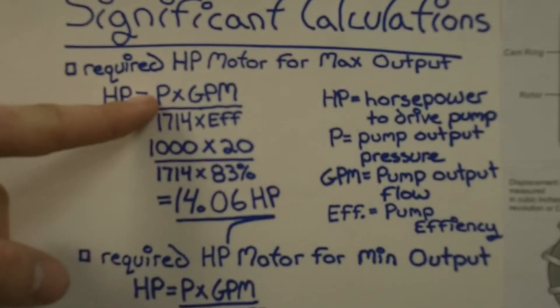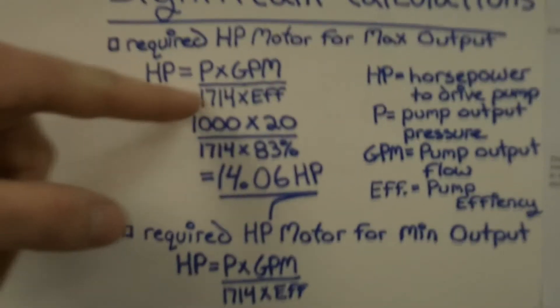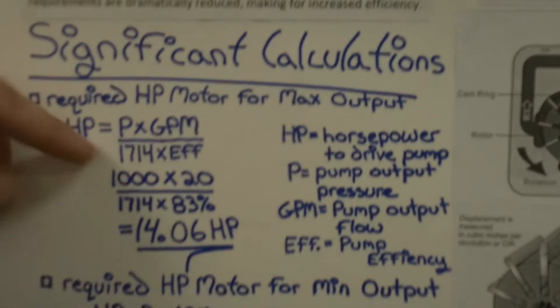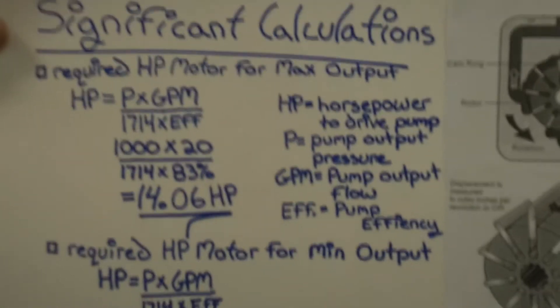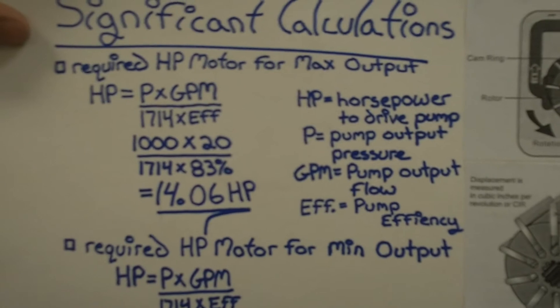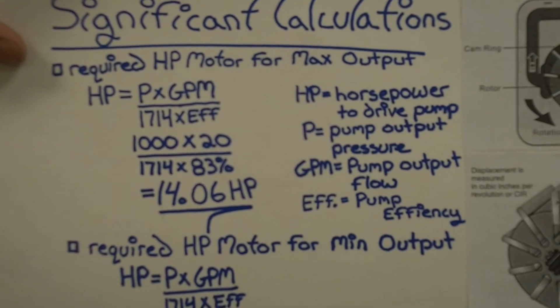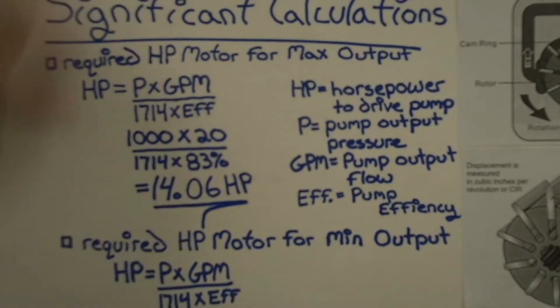Okay. That's a calculation. That's for horsepower. You take pump output times GPM, and then divide that by 1714 times efficiency, and you get that magical number.